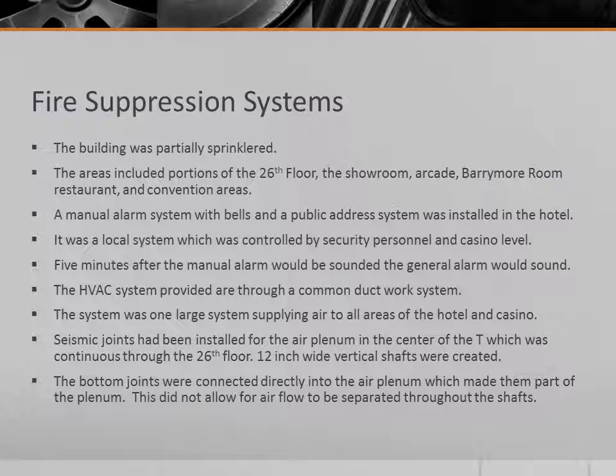The HVAC system provided air through a common ductwork system. It was a large system supplying air to all areas of the hotel and casino. Seismic joints had been installed in the air plenum in the center of the T, which was continuous to the 26th floor. 12-inch wide vertical shafts were created. The bottom joints were connected directly into the air plenum, which made them part of the plenum. This did not allow for airflow to be separated through the shafts.